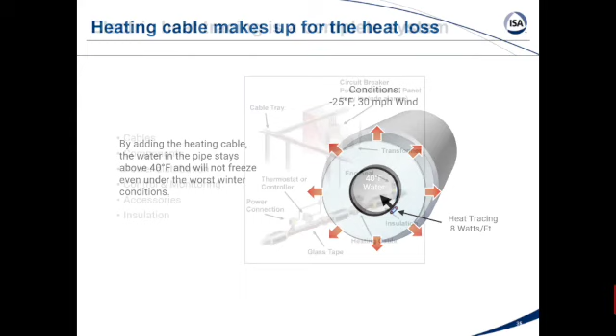Now, the heat tracing system as a whole, when we look at systems, what I was mentioning earlier, I like to get visibility of everything, is that when we see a heat management system or an HMS system, a lot of people will say, oh, well, I just need the stuff that's on the pipe. I want to get involved and understand everything back from the transformer, control and monitoring panel, distribution panel, your cable tray or conduit, all the way to everything on your pipe. I want to understand everything that's involved, because minor changes in any of these elements can result in a lot of cost savings.